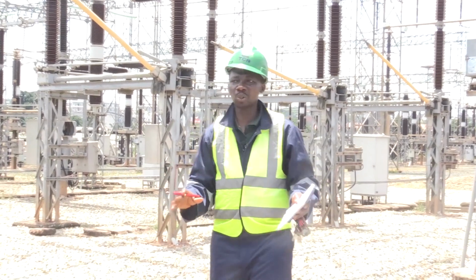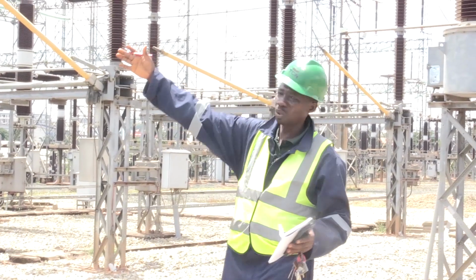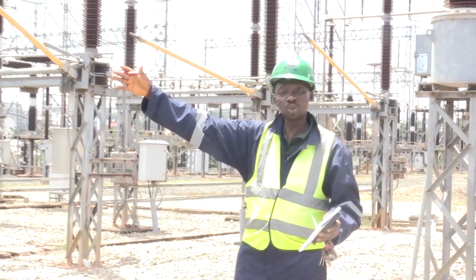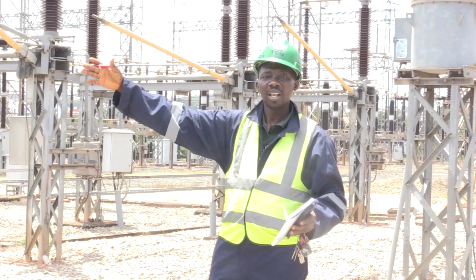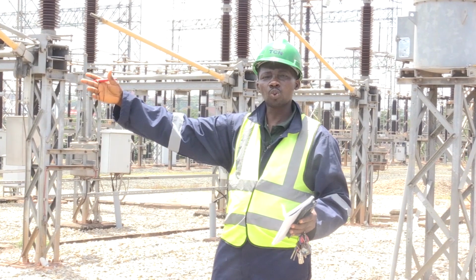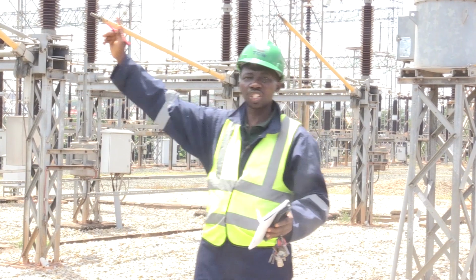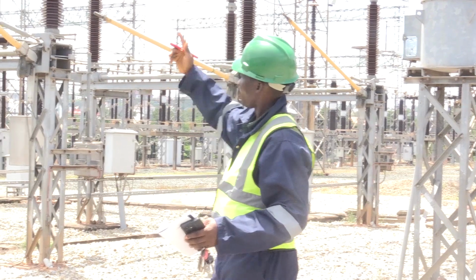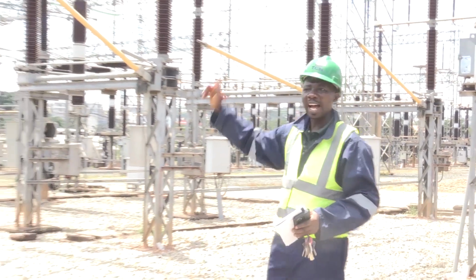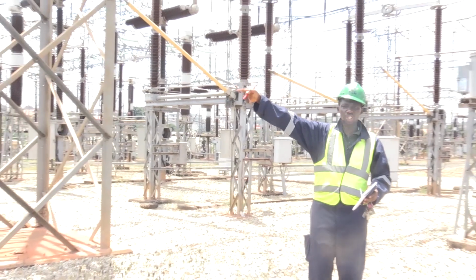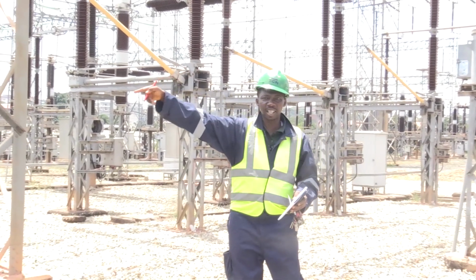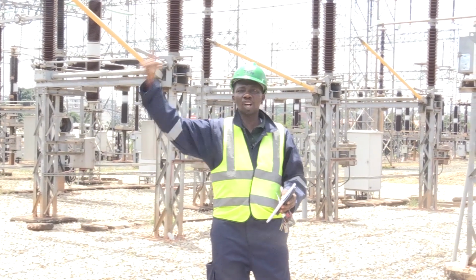But with the ring circuit now, if there's a problem on the single circuit Onitsha 330 line, we can quickly isolate Onitsha. From that point, we open Onitsha and then call our switching station, which is the Ugwaji 330 kV, and tell them to feed us back.